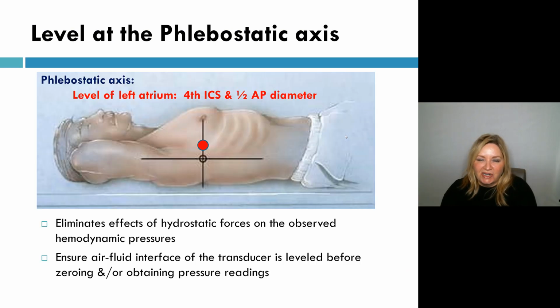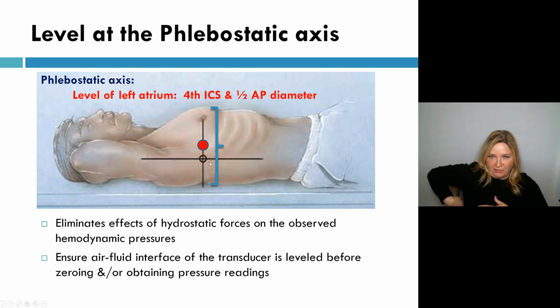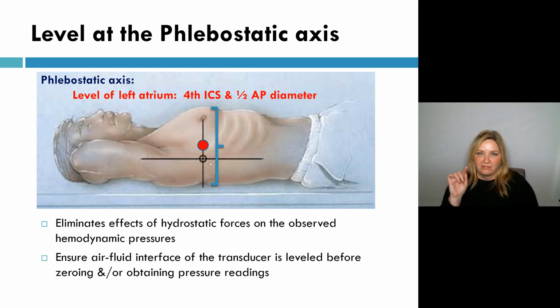Now, once the line gets inserted, you're going to level your transducer at the phlebostatic axis. The definition of this changed a number of years ago, but basically it is the fourth intercostal space, mid-anterior posterior. From the side, look at their anterior posterior and then fourth intercostal. Usually what I've always done clinically is take a Sharpie marker and mark the chest where we're leveling the transducer. And I'll be super honest with you here, one of the things we'll say is, at least if you're off, you're consistently off, right? If you're all leveling to the same X on the patient's chest, you're not going to get wackadoodle numbers all over the place, versus everybody eyeballing where they think they should be leveling the transducer. So that's just a strategy.